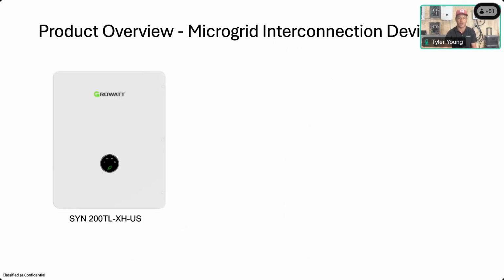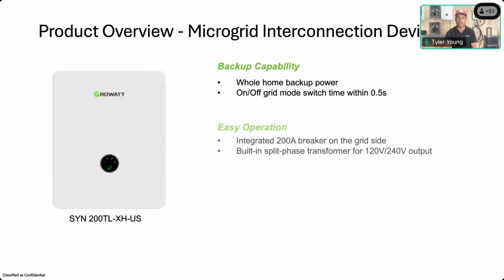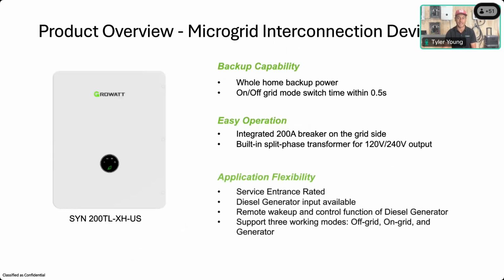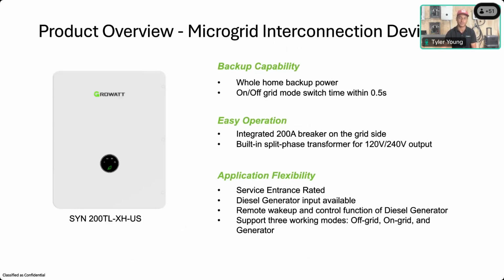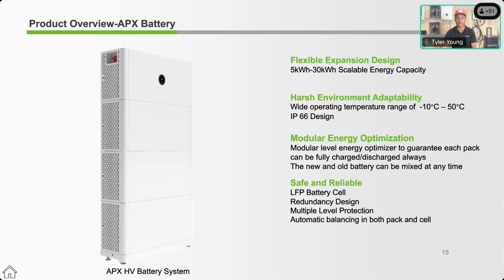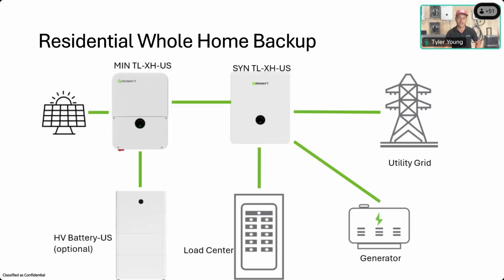Our SYN 200 amp pass-through transfer switch, which allows generator function, whole home backup in 0.5 seconds. And then, of course, the APX battery, which pairs with both of those. Stackable, it's battery ready, so you don't need a battery. Stackable from 5 kilowatts up to 30 kilowatts. So you can add on as you go or as you need for battery backup. All of these are outdoor rated, IP66 rated. Here's a typical whole home backup grid design. As you can see, generator as well.